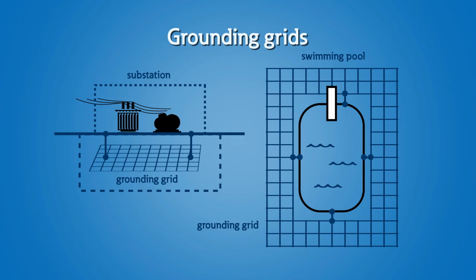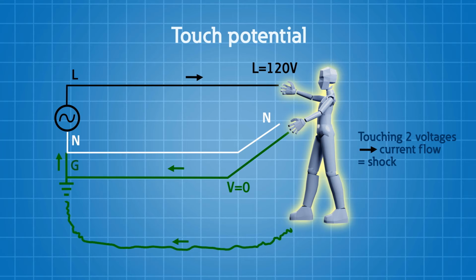So we expand this concept. If you think about touch potentials or step potentials and keeping things at the same potential, you can think about this in regard to substations, where we establish a grounding grid underneath the substation, or around swimming pools, where we're doing equipotential bonding. This will reduce the likelihood of voltage potentials, and we understand that a potential difference between two voltages is what's going to drive current. So if we can reduce or eliminate that potential difference, we can reduce the likelihood of shock, and we can reduce the likelihood of damage to electrical equipment.